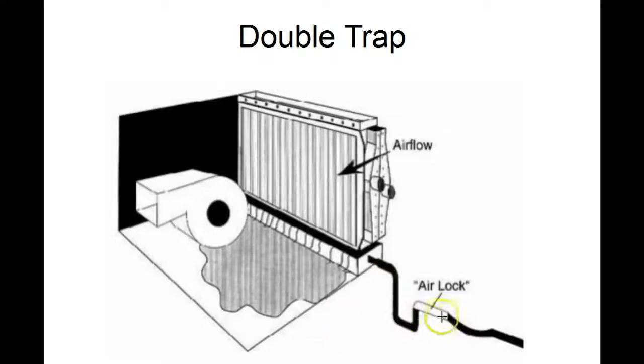This bow could be over the course of 15, 20 feet and not very noticeable at all, just a little tiny bow. That creates a double trap condition. What happens is we get an airlock in here and once you get an airlock between these two columns of water, it will no longer allow this system to drain. This is just the same as a too tall trap. It will back up into the drain pan and then flood into the air handling unit.